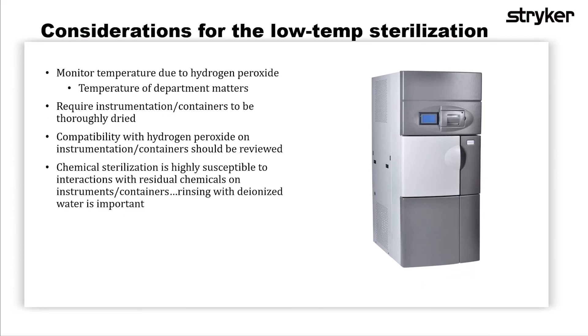Considerations for low-temperature sterilization — these are true of all forms, specifically those that utilize hydrogen peroxide. Hydrogen peroxide is sensitive to temperature, so temperature matters for all modalities. Instrumentation must also be completely dry, as hydrogen peroxide will grab hold of moisture within your load and could lead to an aborted cycle. We always want to consider compatibility of instrumentation as well as containers. And since this is chemical sterilization, it is highly susceptible to interactions with other chemicals, so rinsing with deionized water is an important step before putting instrumentation into a low-temperature sterilizer.